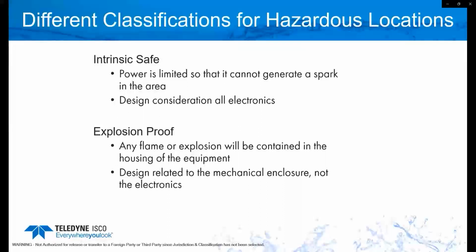Some of the older things we've done in the past used explosion-proof equipment — sometimes it looks like a submarine, or a pretty rugged type of enclosure. The purpose is that any explosion or flame inside the housing of that equipment is contained within it. So explosion proof is about containing the blast, while intrinsic safe is about limiting the amount of power going into that area. Both have to be taken into account during the design phase, but explosion proof is more mechanical, not electronics.